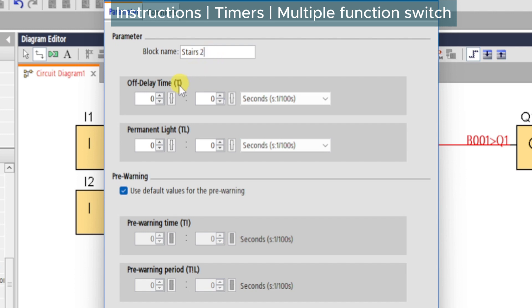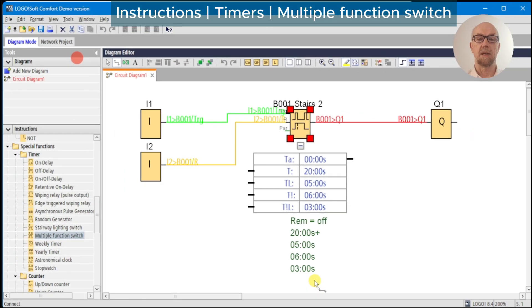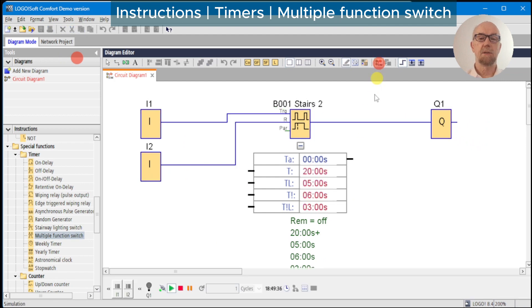We have the off delay time which we'll set at 20 seconds. We have the permanent light time which we're going to set at five seconds — so if we hold the switch on for five seconds the light will remain on. We'll override the pre-warning defaults: six seconds before our 20 seconds are up we're going to blink the lights off, and hold them off for three seconds — though that's longer than we'd use in a real application. Switch on simulation mode.